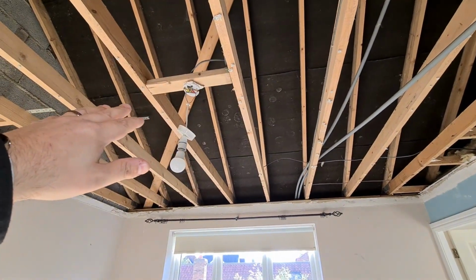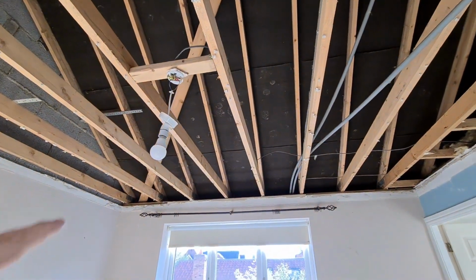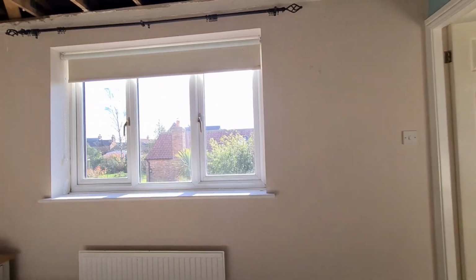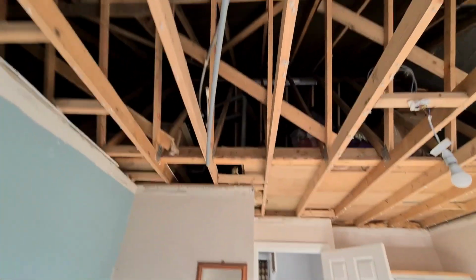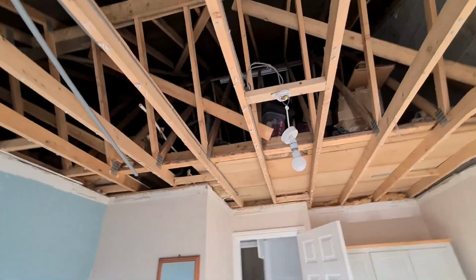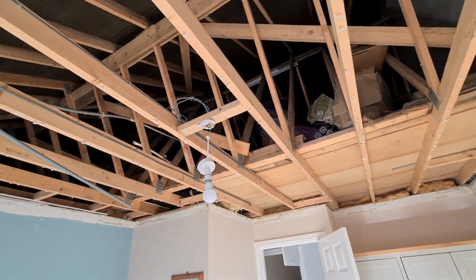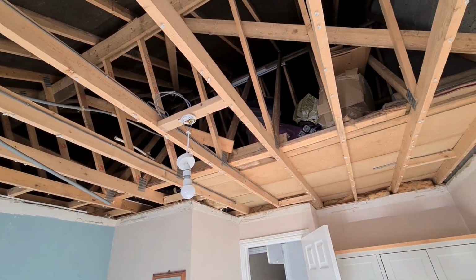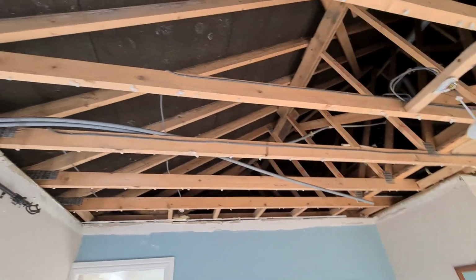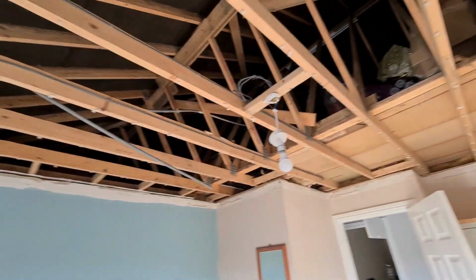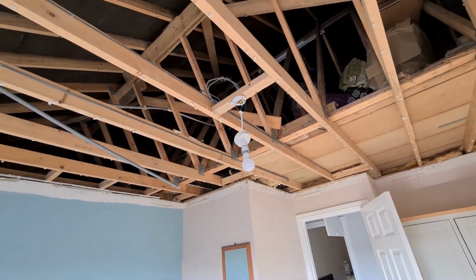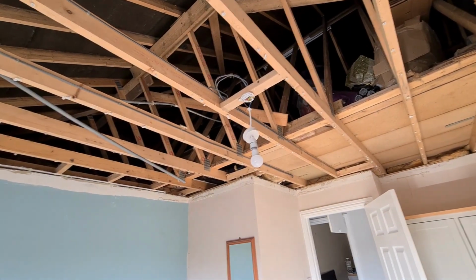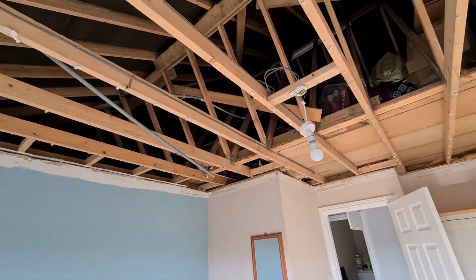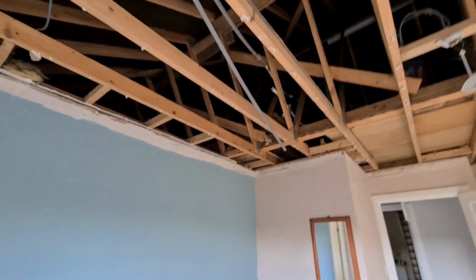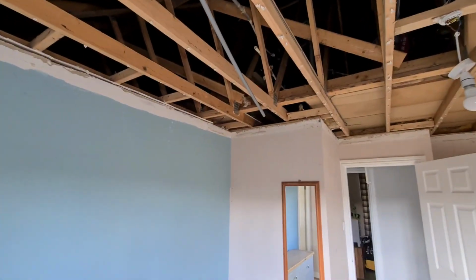When I first inspected this, the ceiling was up, but there are a few issues with the wiring. It's nice that the ceiling's down because you can kind of see exactly what's what without having to go into the loft space. It's only this side of the property where the ceiling's out, but looking at it, the original install seems to have been done fairly well. You can often get a good feel of it just from looking at the clipping of the cables, the way they're dressed in, the accessories. It's always a nice way of judging what the wider install's like.